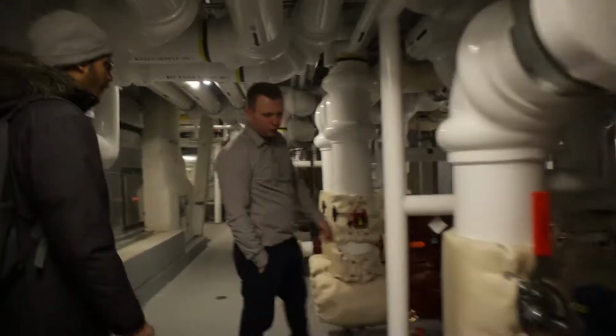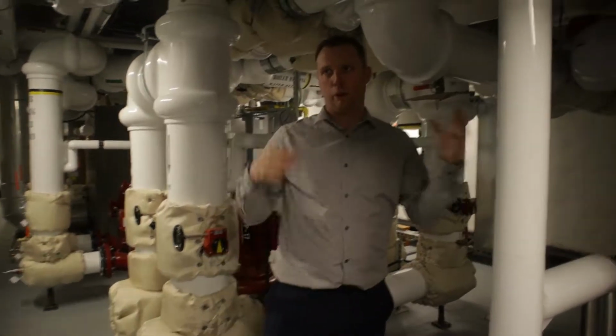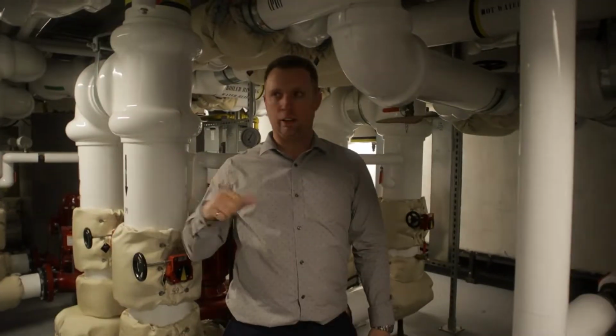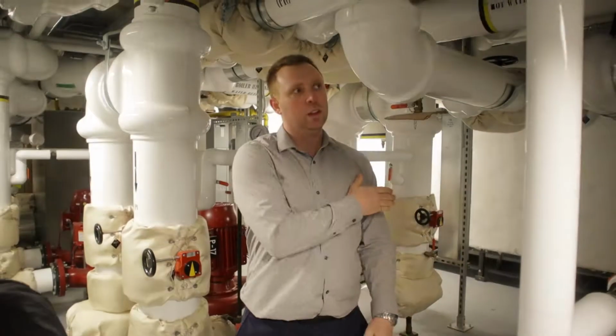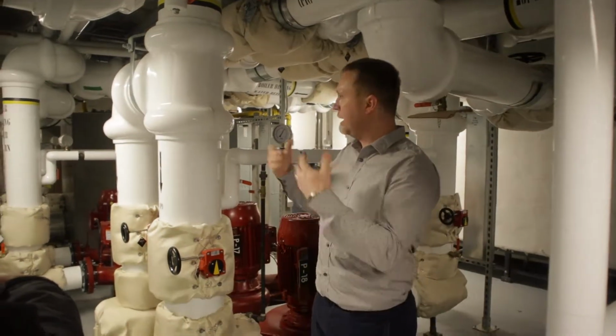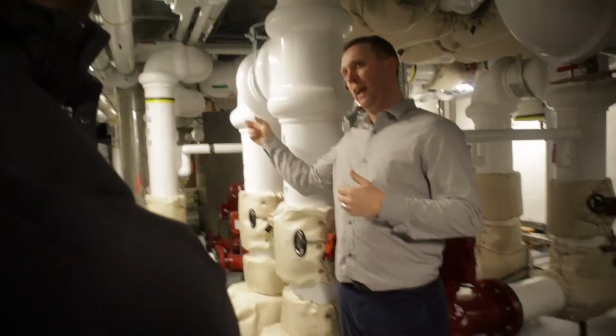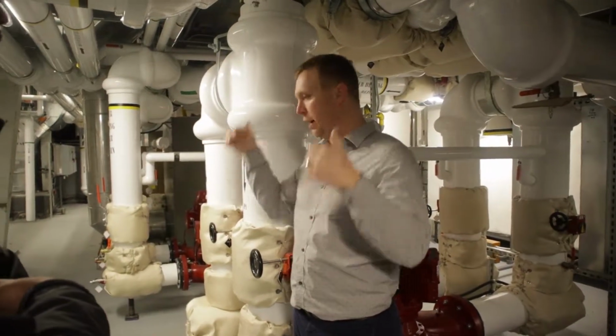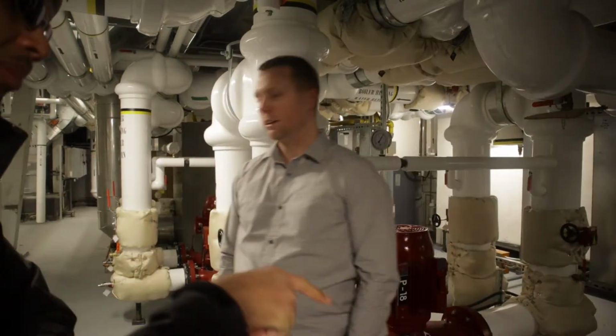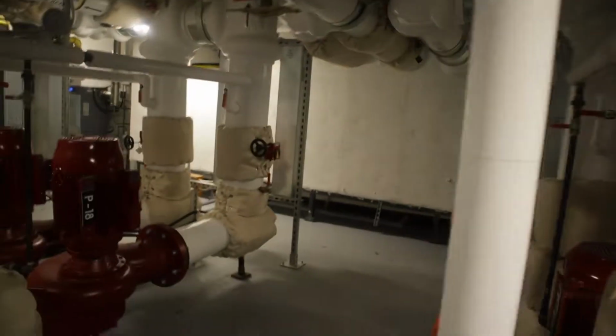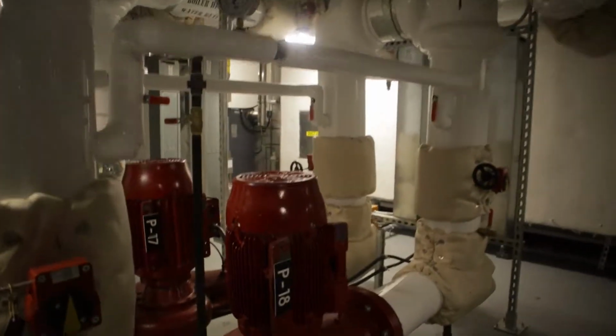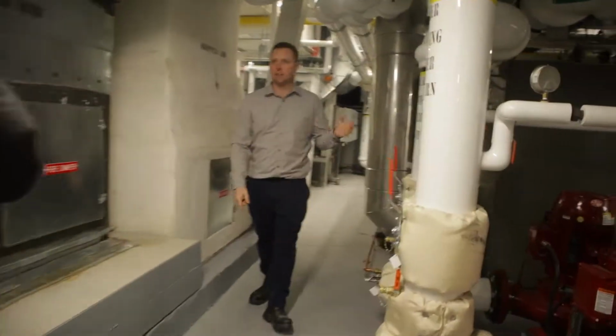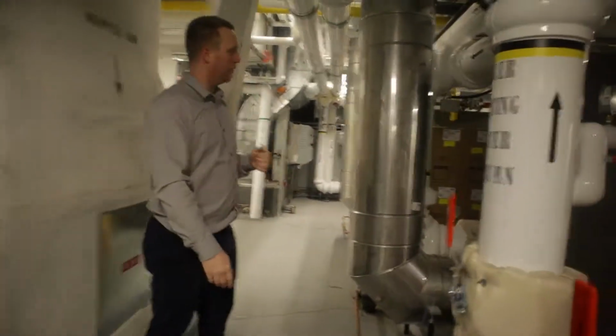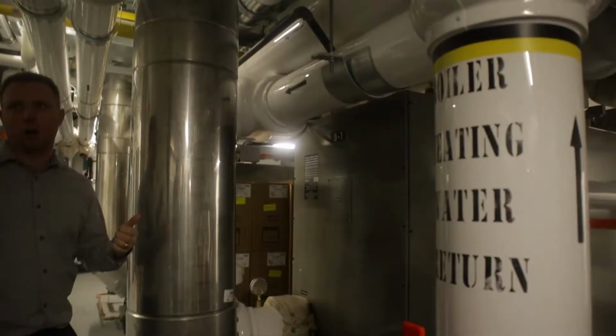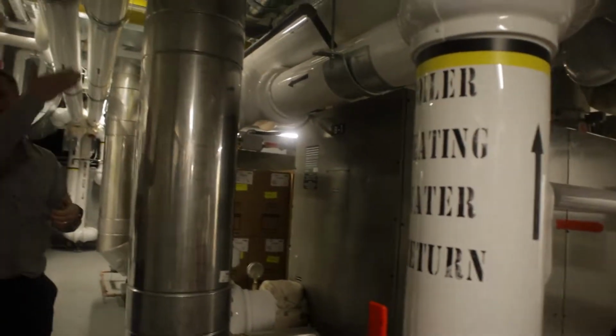We actually have heat pumps downstairs in the basement, and we take salt water from the ocean and put it through a heat exchanger. It goes to either the heating or cooling side of the heat pumps - about 12 of them in parallel. From there it gets heated up, sent here, warms and cools the air, and distributes throughout the building. There are lots of pumps going to different systems, and over here are the boilers. On a day like today when the sun's shining, even though it's cold, the building still warms up. If the sun isn't shining, the heat pumps still work, but the boilers top it up to get the right temperature.